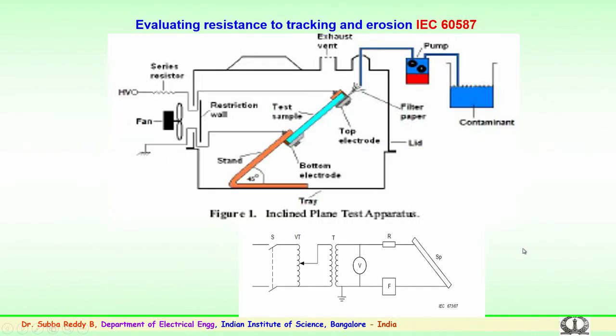Further, to evaluate the resistance to tracking and erosion, there is a standard, IEC 60587, which clearly gives the procedure to perform the experimentation on the silicon rubber or high temperature vulcanized rubber, where very clearly the 45 degree arrangement has to be made to fix the sample. This is the sample which is being fixed with the 45 degree arrangement.